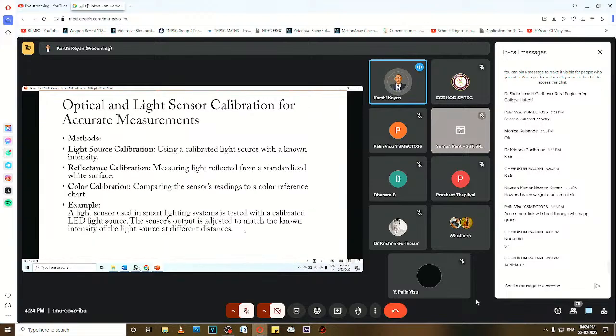Next, optical and light sensor calibration for accurate measurements. Light source calibration: using a calibrated light source with a known intensity. Mostly the calibration is done based on a reference value. But each reference value has some standard, and that reference must be calibrated against national level standards. Actually, secondary standards are compared to the primary standards. So the accurate value is held by the primary standards, and this will be kept.